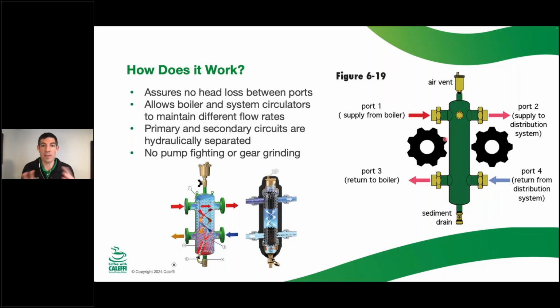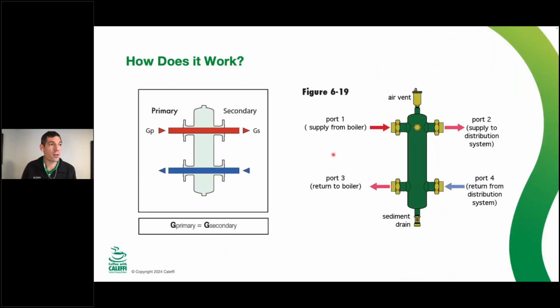It is just something that's separating the flow rates. So it fixes the GPM problem. It doesn't fix the temperature problem. If that's something that you're looking to solve, you'd need to use another component in the system to address low temperature protection for radiant or something like that. So what are the flow scenarios inside of a hydro separator?